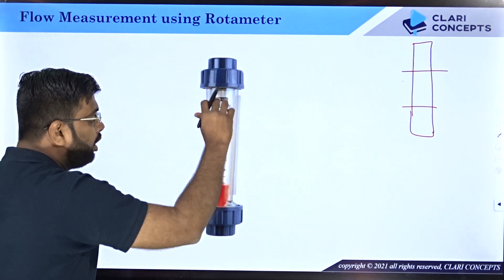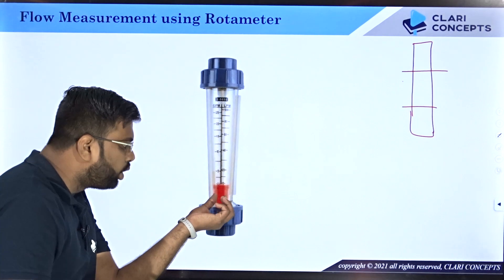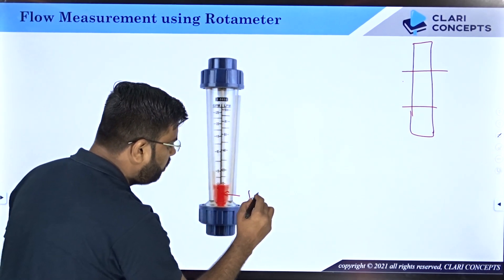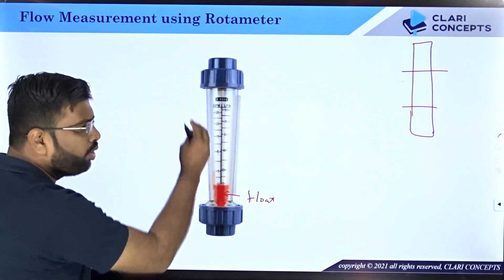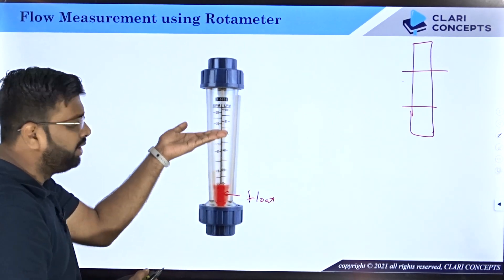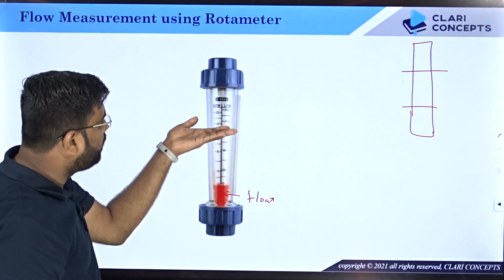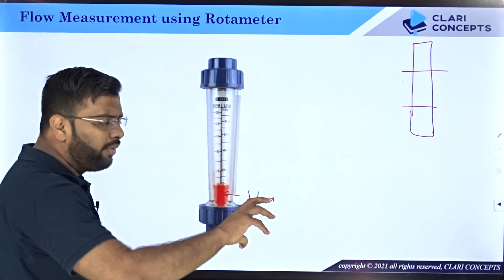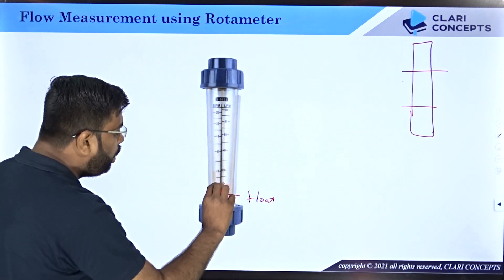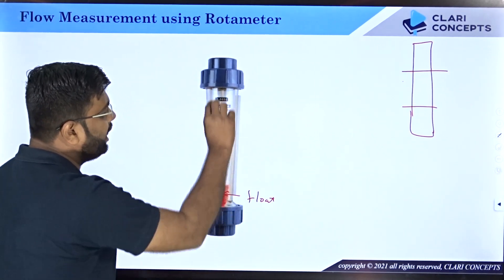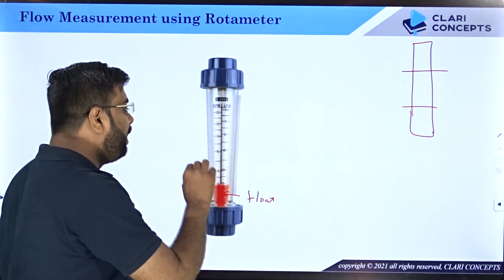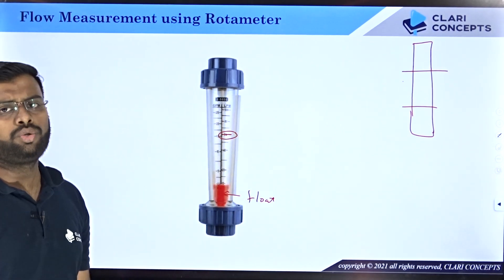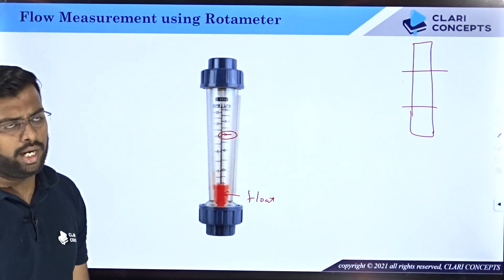In a rotameter there is a scale and a float — the orange-colored component is the float. The moment water starts flowing through it, the float rises and stops at a particular location corresponding to the flow rate. Depending on the position of the float, you can read off the flow rate — for example, so many liters per minute or cubic meters per second.